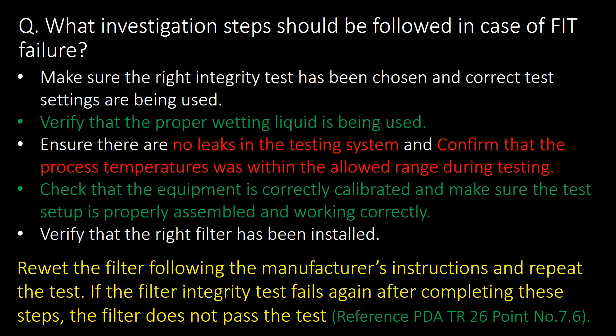What investigation steps should be followed in case of filter integrity test failure? Make sure the right integrity test has been chosen and correct test settings are being used. Verify that the proper wetting liquid is being used. Ensure that there are no leaks in the testing system and confirm that the process temperatures are within the allowed range during testing. Check that the equipment is correctly calibrated and make sure the test setup is properly assembled and working correctly. Verify that the right filter has been installed, rewet the filter following the manufacturer's instructions, and repeat the test.